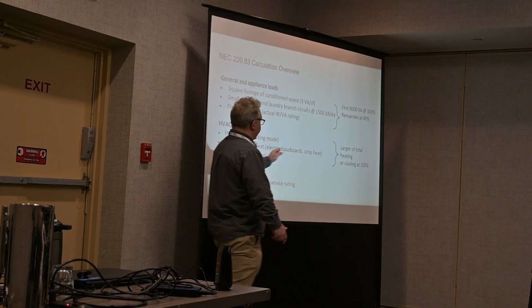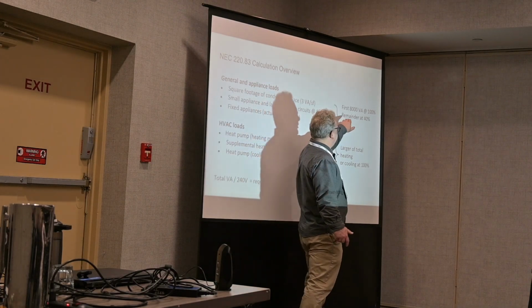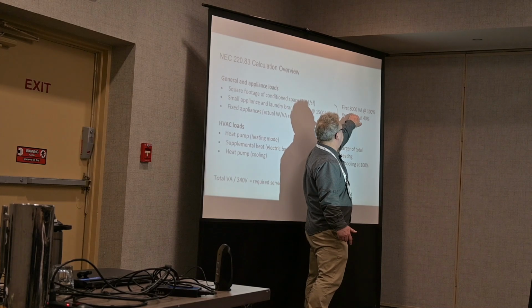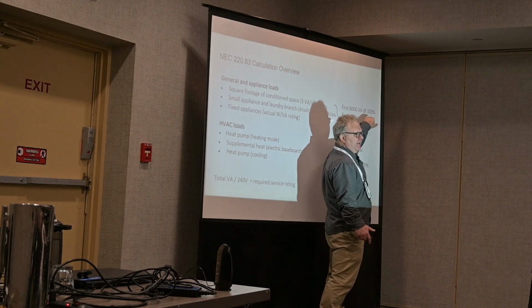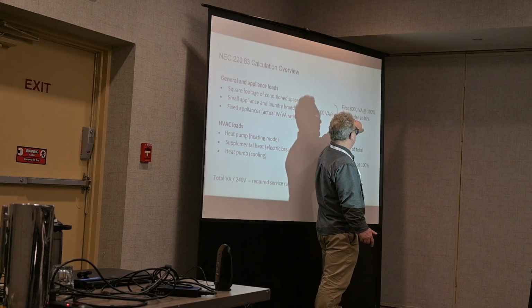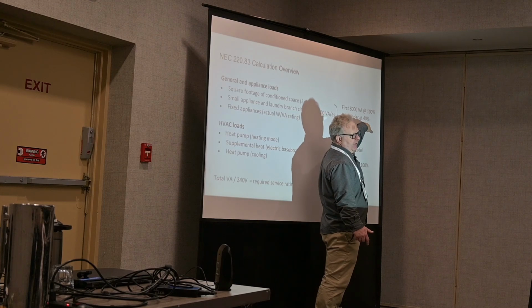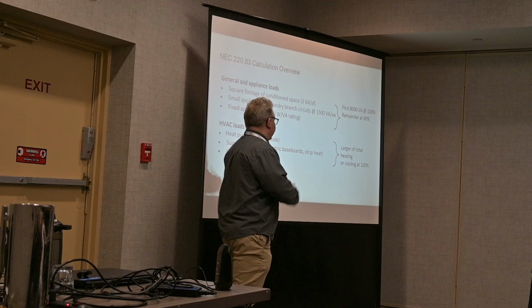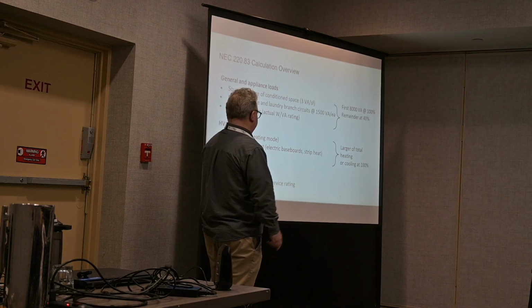What this calculation does is, and I'll go over the details in the next slide, you add up the first 8,000 VA and count those at 100%. And then general and appliance loads that are over 8,000 VA get derated to 40%. And that's to recognize the fact that not all these are going to be used at the same time.